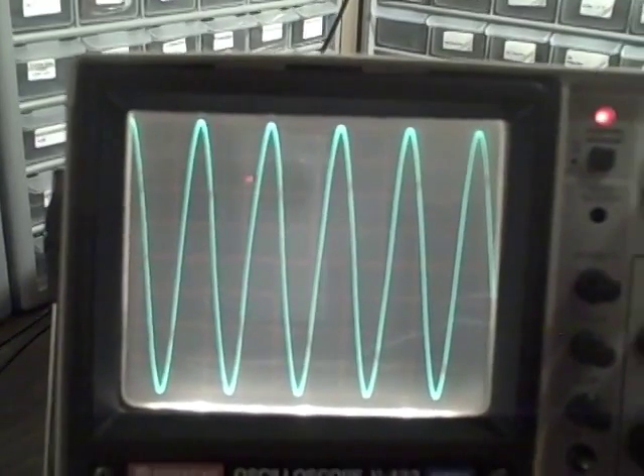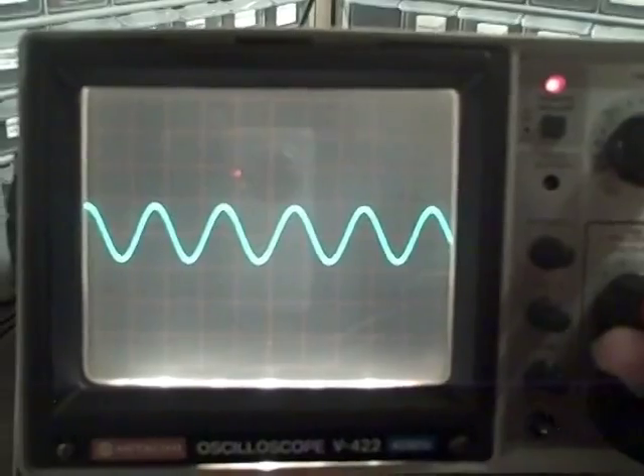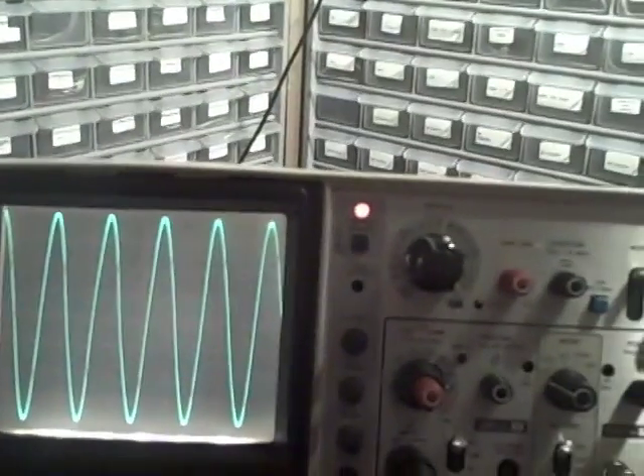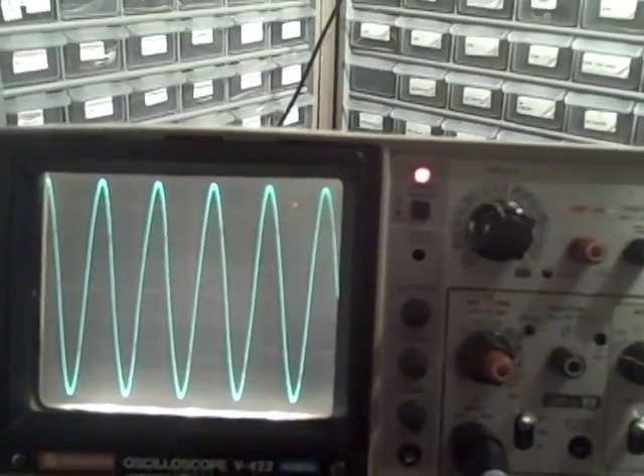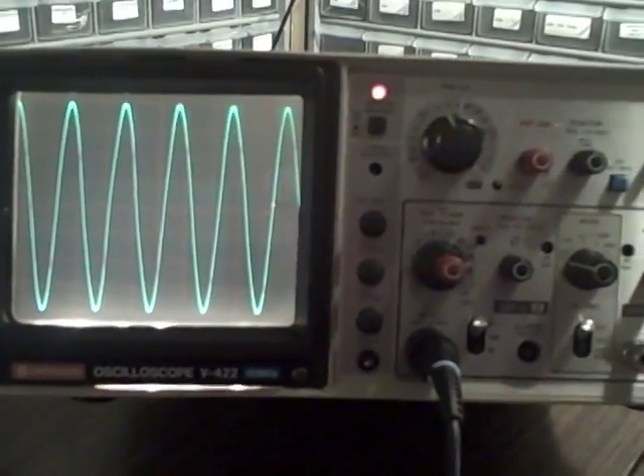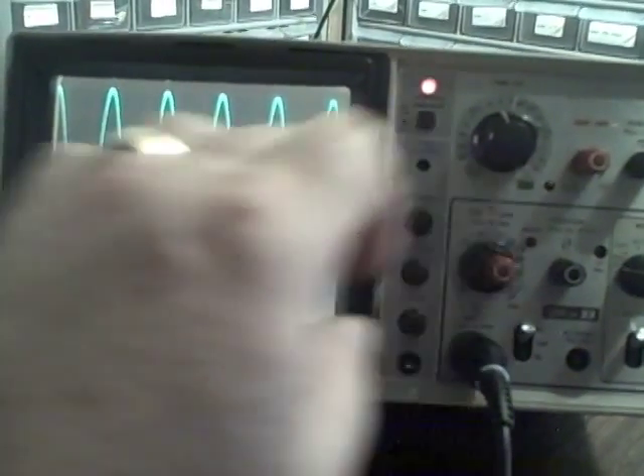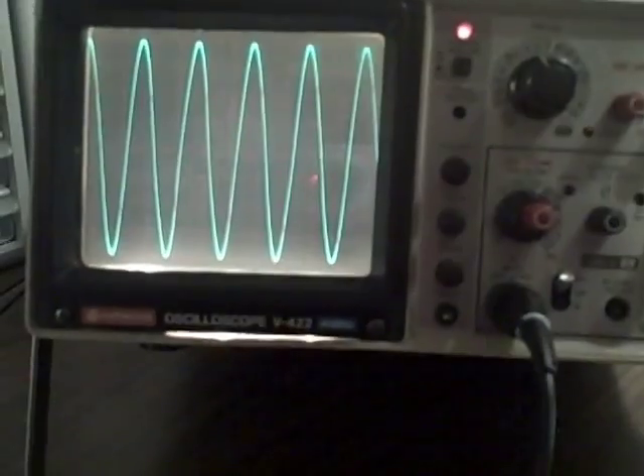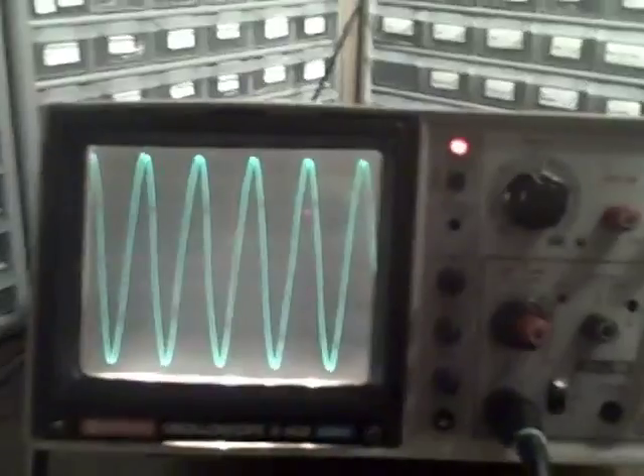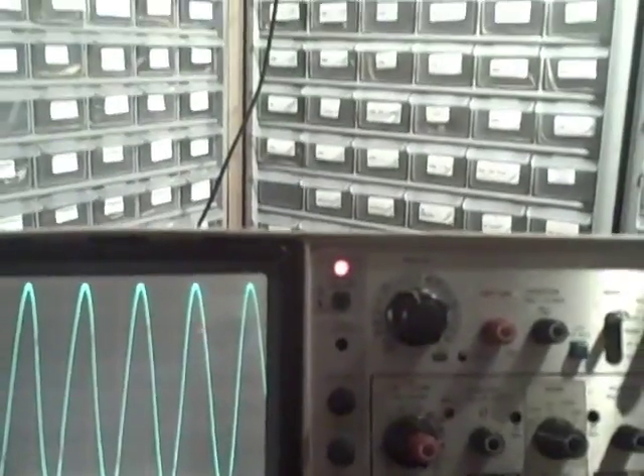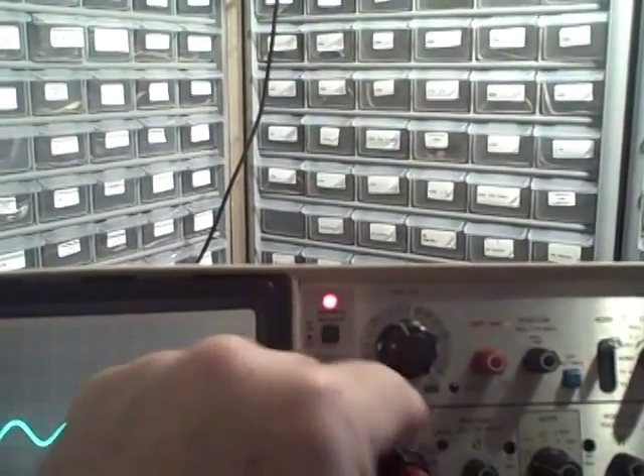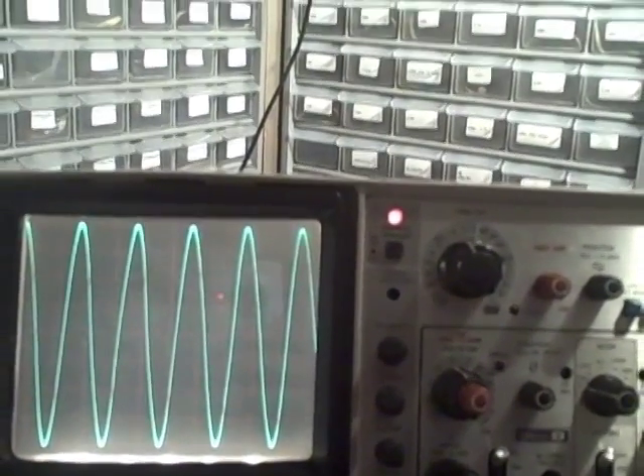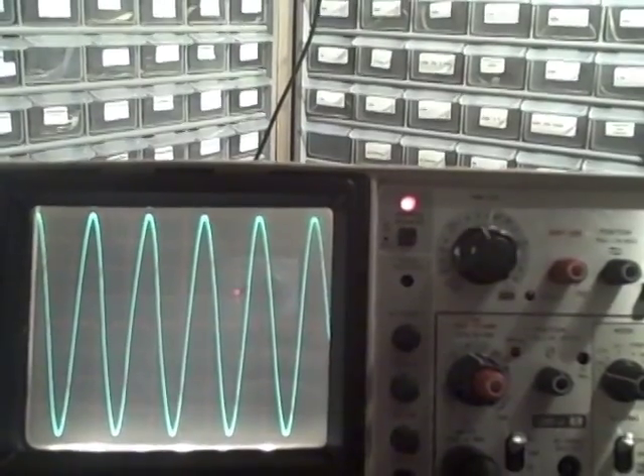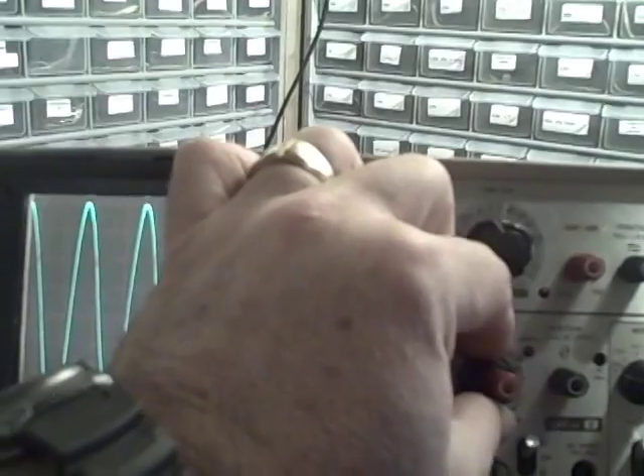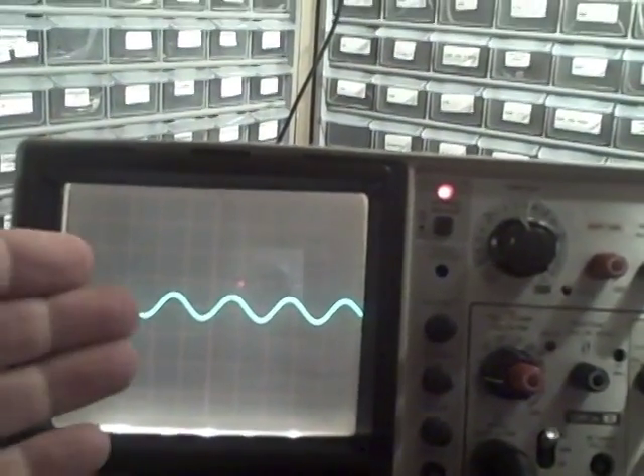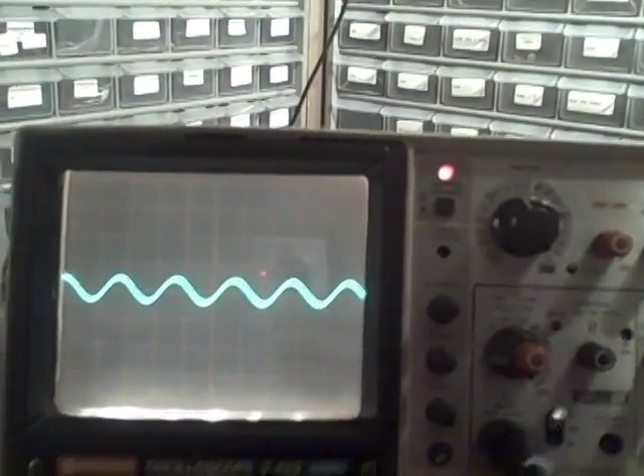Let's take ourselves back, put our divider back on, and we're going to take ourselves to 20 millivolts per division. We are now feeding in 800 millivolts from the standard. We are dividing it by 10. We are getting, on the 20 millivolt per division scale, we're up 4 and down 4. So it's 4 times 20 is 80 millivolts. 80 millivolts is 1/10 of 800 millivolts, which is what we're feeding in. So again, we're scaling perfectly. Let's go ahead and raise ourselves up from 20 to 200 millivolts per division, and we'll take off our divide by 10. Once again, we're spanning plus and minus 4 divisions up and down. Let's take ourselves up to 2 volts per division, and we see ourselves coming up 0.4 in each direction, which is exactly what we would expect.